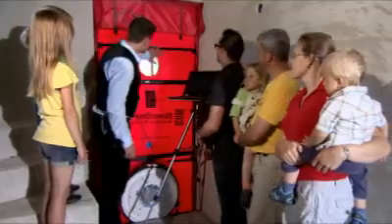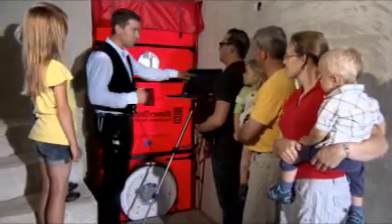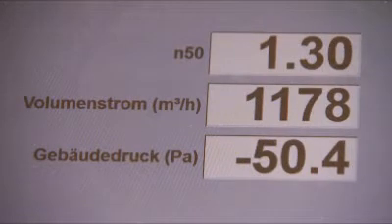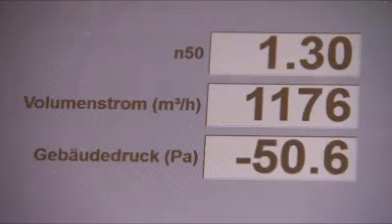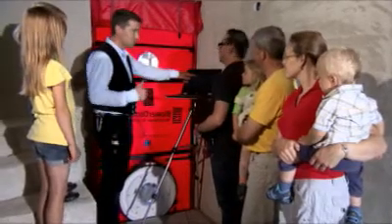Finally, the craftsman repeats the blower door measurement in the presence of the building owner and the architect. What improvement has been achieved by the corrections? The air change rate is now well below the required maximum of 1.5.